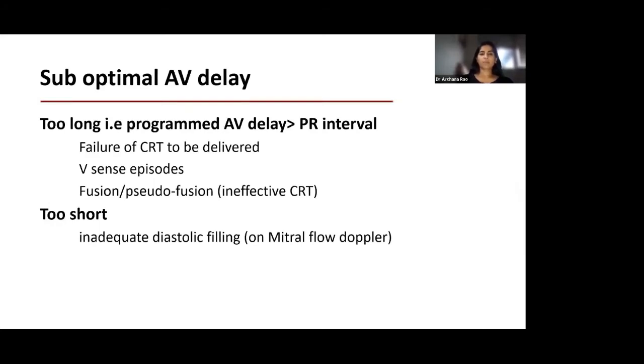So when we talk about suboptimal AV delay, obviously the AV delay is the time between your atrial delivery and your ventricular delivery on a pacing system. When that AV delay is too long, i.e. the programmed AV delay is greater than the intrinsic PR interval, there is failure of CRT to be delivered. Ventricular sense episodes happen because intrinsic conduction is happening, inhibiting the delivery of the CRT. There's also the possibility of fusion and pseudofusion, resulting in ineffective CRT. When this does happen, it does impact on battery longevity without any potential gains for the patient.